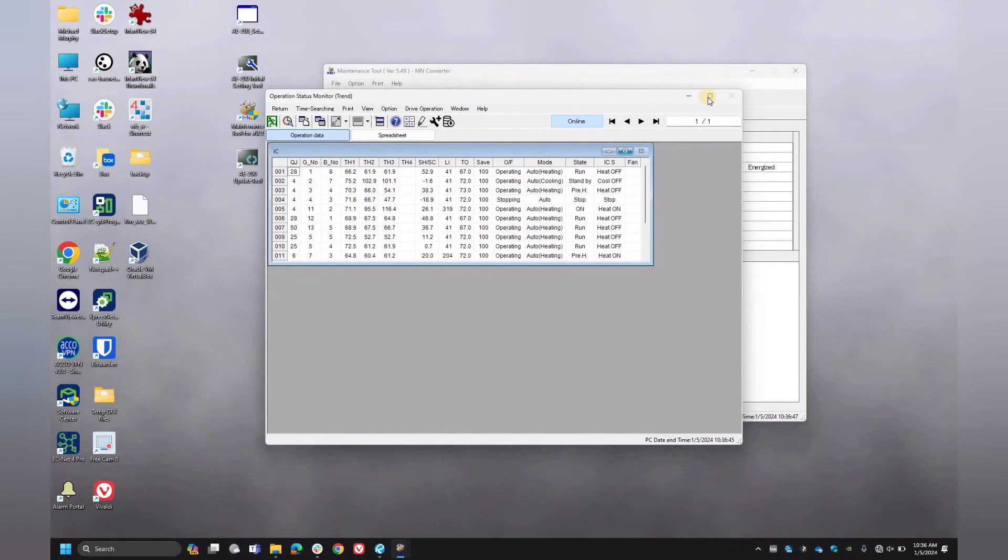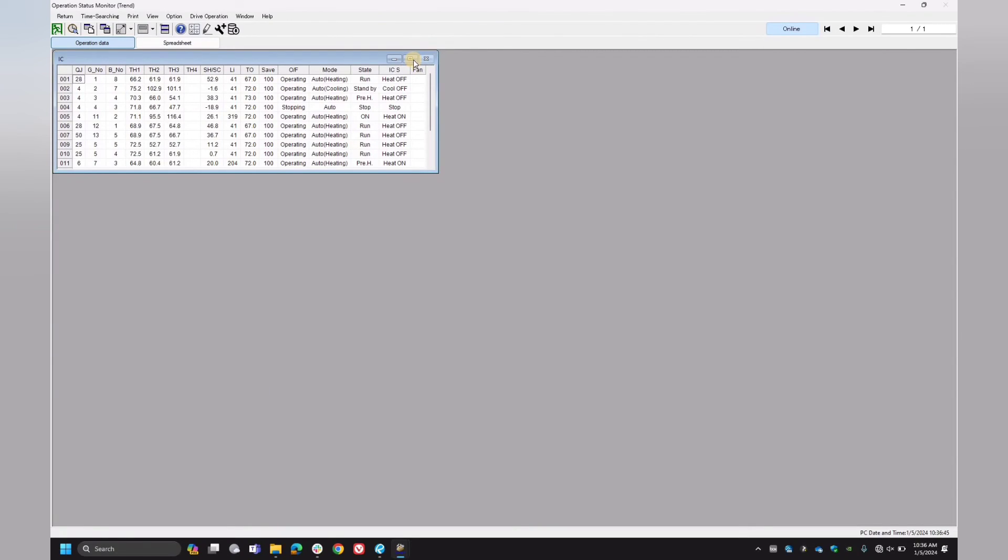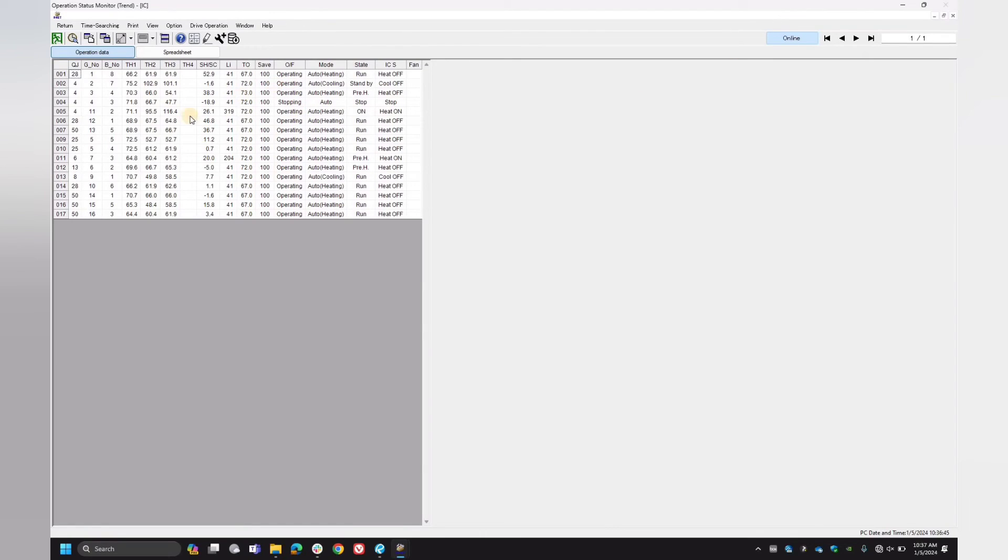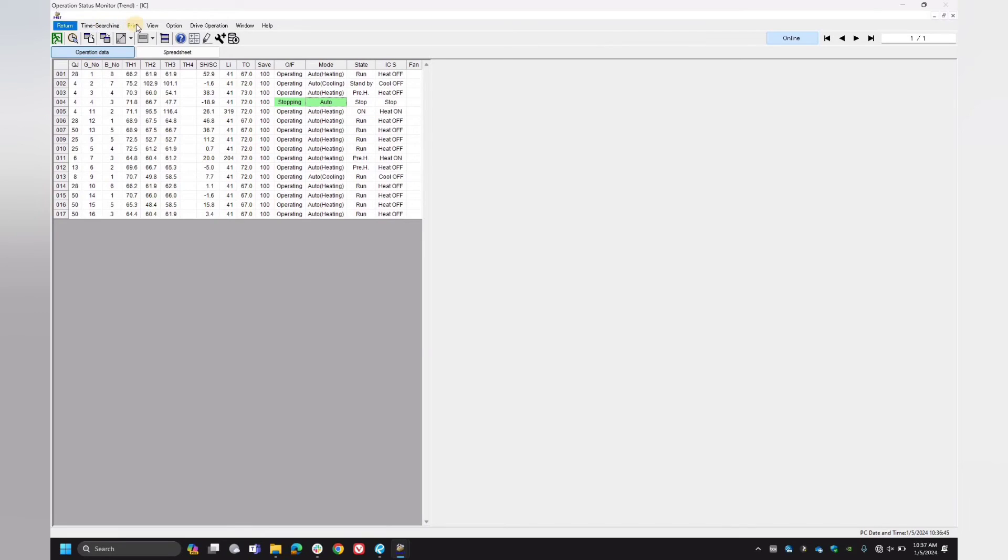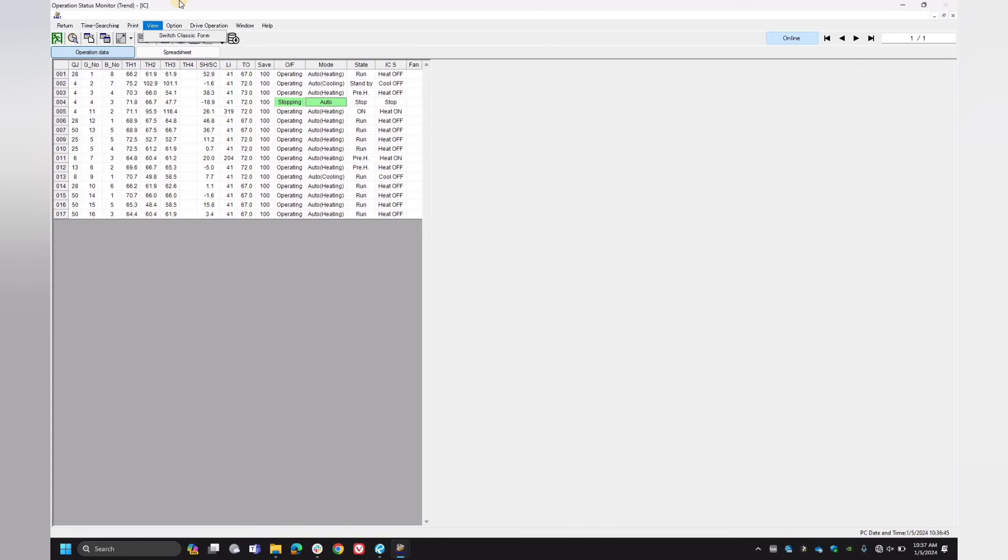And if you want to just monitor just the VRFs, you'll select just all of the icons that have the IC. And here as you can see, here's a summary of all of my different VRF units here. So as you can see, most of them are operating except for this unit number four, which is stopping right now. But it is in auto mode. But this is really handy to have. And you can save this as a file. You can print it and you can save it as a PDF if you want. So that way you can have this on your record prior to cutting over a new system.